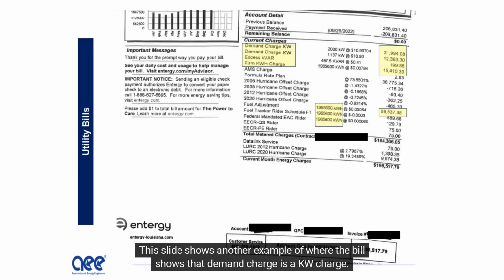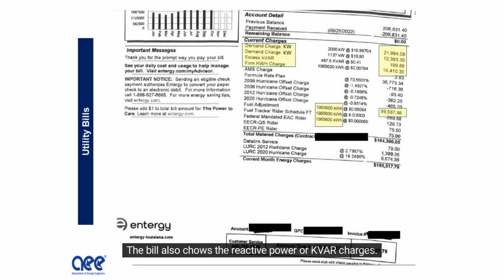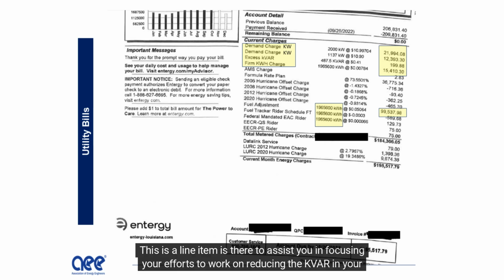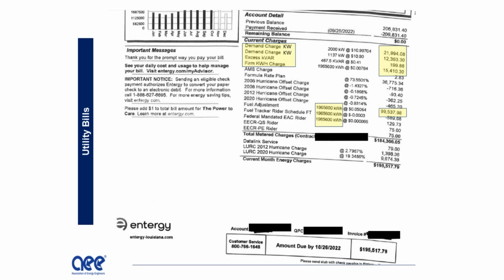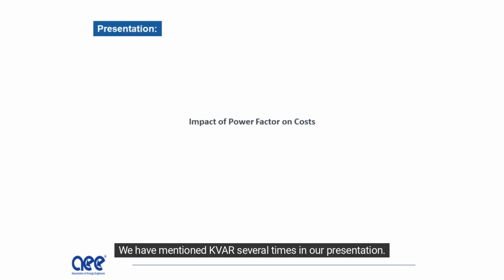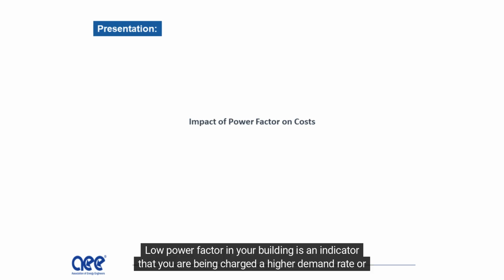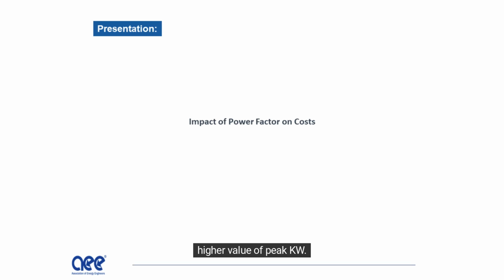This slide shows another example of where the bill shows that demand charge is a kW charge. The bill also shows the reactive power or kVAR charges. This line item is there to assist you in focusing your efforts to work on reducing the kVAR in your building. We have mentioned kVAR several times in our presentation. This takes us into the topic of power factor. The presence of kVAR is the reason for low power factor. Low power factor in your building is an indicator that you are being charged a higher demand rate or higher value of peak kW.